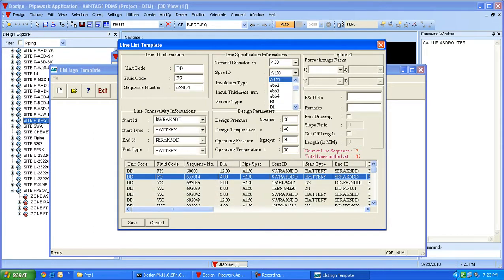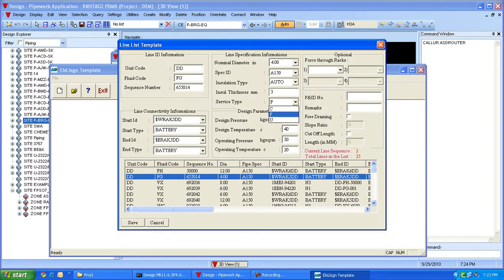Line specification like nominal diameter can be provided. Spec information is available in the pipe spec.dat file. Insulation can be provided, or it could be given as minus one so that the router will automatically calculate it based on the temperature. Service type of the pipe should be provided. Temperature and pressure options are optional, and this is how entry of any line into the line list is done.